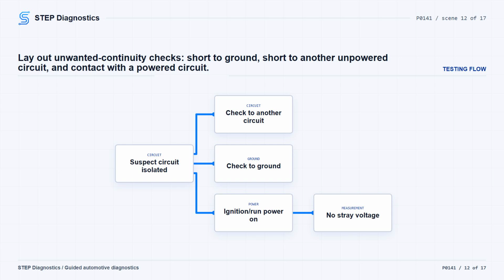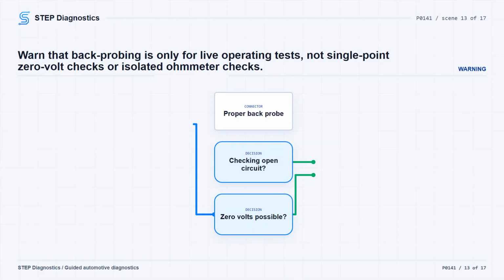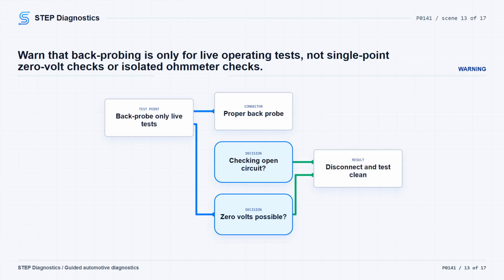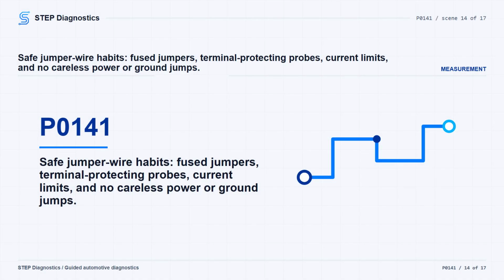Only back probe when the circuit has to be tested under real operating conditions. Use back probes made for that job, and remember that a poor probe contact can look like a circuit fault. For a single point voltage check, where 0 volts is a possible result, disconnect the circuit and test normally instead of back probing. For continuity or open circuit checks with an ohm meter, disconnect and isolate the circuit instead of back probing. When using jumper wires, always use fuse jumpers.